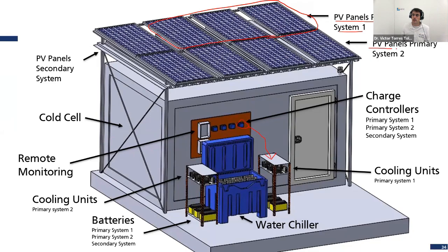Okay, then we have a primary system 2, because we have here 2 primary systems in this system. The second primary system has another charge controller and is delivering energy to the compressors on this side. And you see another charge controller is not utilized in this one, but it depends how many cooling units you have, right? Because the system is modular. Okay, and then we have these 2 PV panels here on top that are still missing. These ones are for the secondary system, right? So you see here, secondary system. They also have their own charge controller, and then they deliver energy to the water pump and to the heat exchanger inside the cold room, with the door.